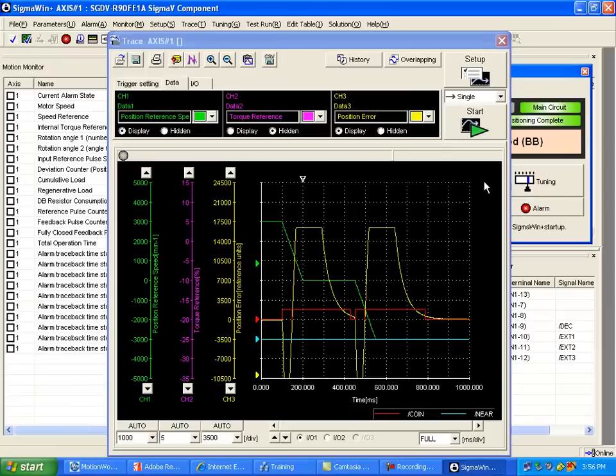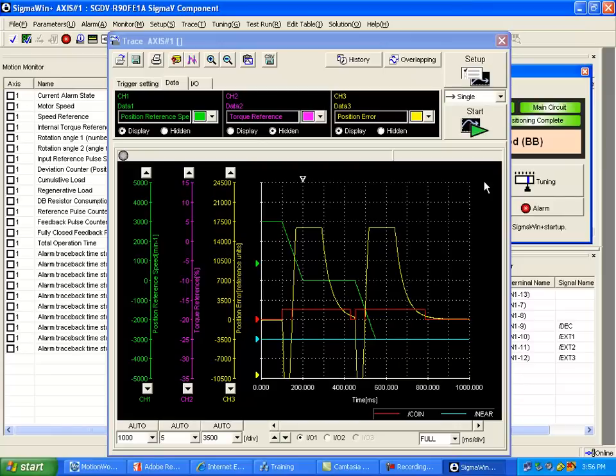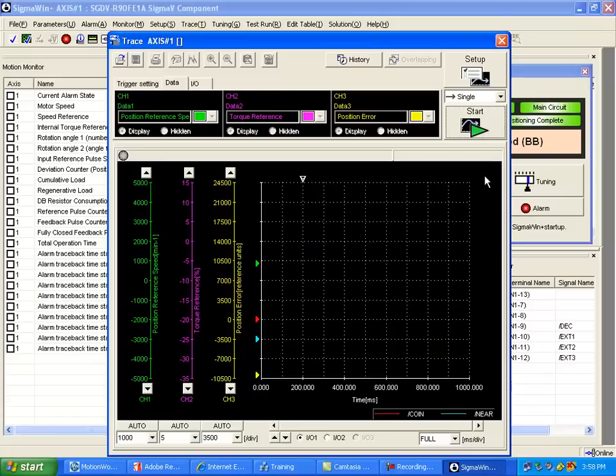Whereas the out-of-the-box parameters were optimized for a dynamically changing inertia load, the advanced auto-tuning parameters were optimized for a static load. In this case, the 20-to-1 inertia ratio. So now let's go ahead and trace using the advanced auto-tuning parameters we just loaded. Let's select Start in the trace window again.